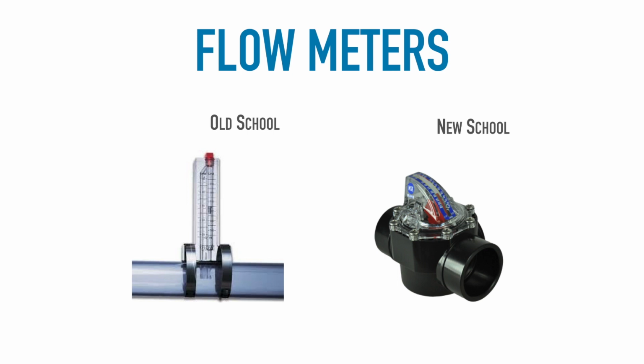Water flows through, pulls that tongue down, and reads at a 98.2, I believe, percent accuracy level on that FlowViz system. Incredibly accurate. The thing that's also really nice about these is you can install them on 1 foot of pipe. You can install them on 20 feet of straight pipe. You can install them on a slope. You can install them vertically. You can install them upside down. Wherever you install these in your system, they are still going to give you that 98% accurate read.